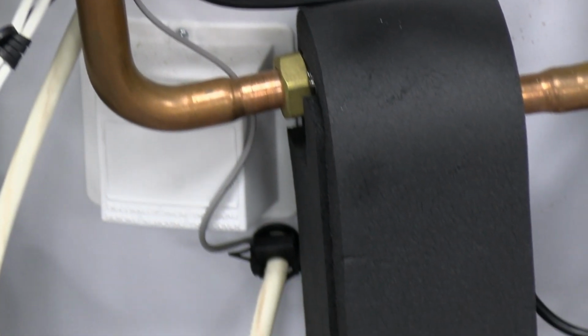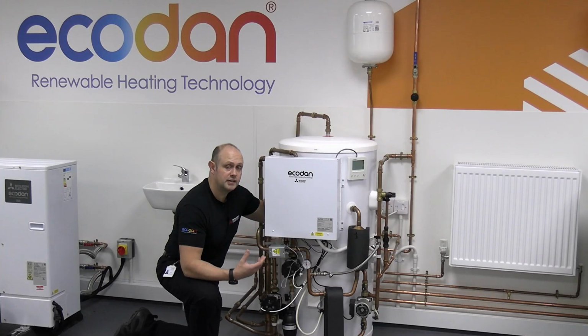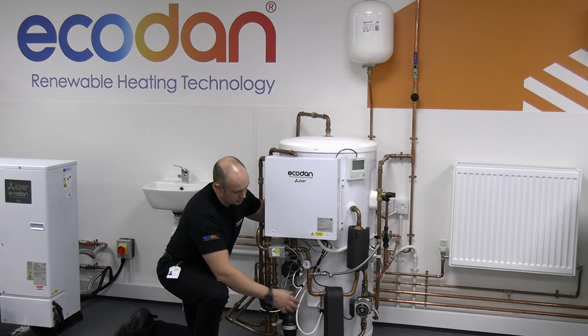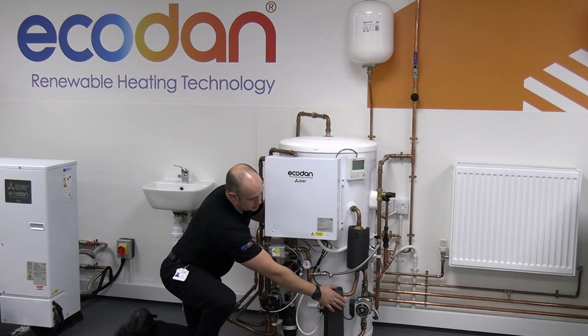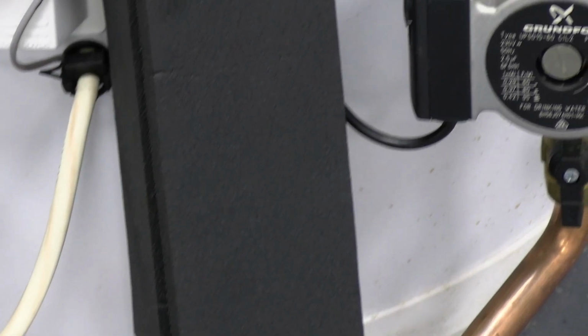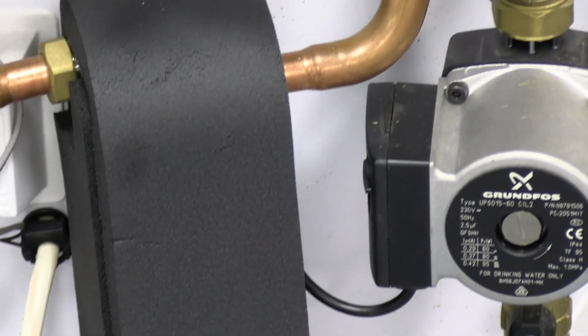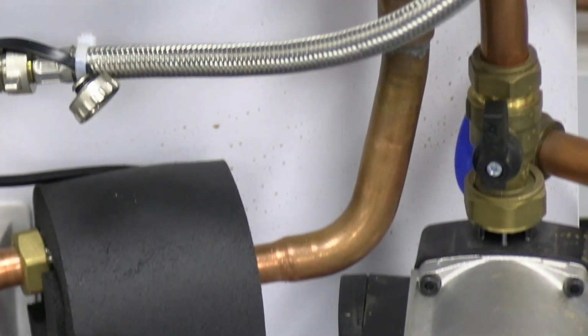So on Mitsubishi cylinders, we don't have an internal coil because that's reliant on natural convection, which is a bit of a slower way of actually heating up that hot water. Whereas you can go to forced convection, we can force that water in and out of the actual cylinder, past that plate heat exchanger, and that improves our heat up time on the cylinder. So along with the actual plate, we've also got a pump, which is pumping the water in and out of the actual cylinder, and that's a WRAS-approved pump.